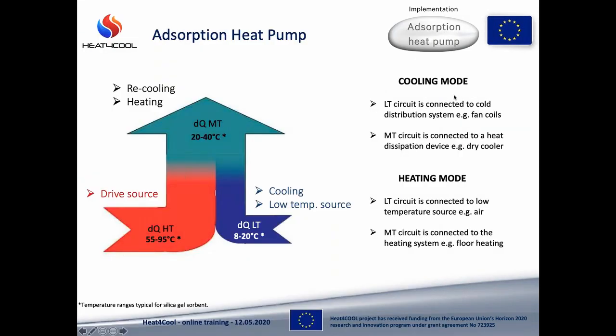Till now, I have focused on cooling, but it is also possible to use the adsorption heat pumps for heating. All you need to do is to set a corresponding operation mode on the HMI and connect the external HT, MT, and LT circuits a bit differently than for cooling. In the heating mode, the machine's LT circuit should be connected to the low temperature heat source, and MT should be connected to the heating system, for example, floor heating. There are no changes in HT. This circuit should be connected with a high temperature heat source as before.